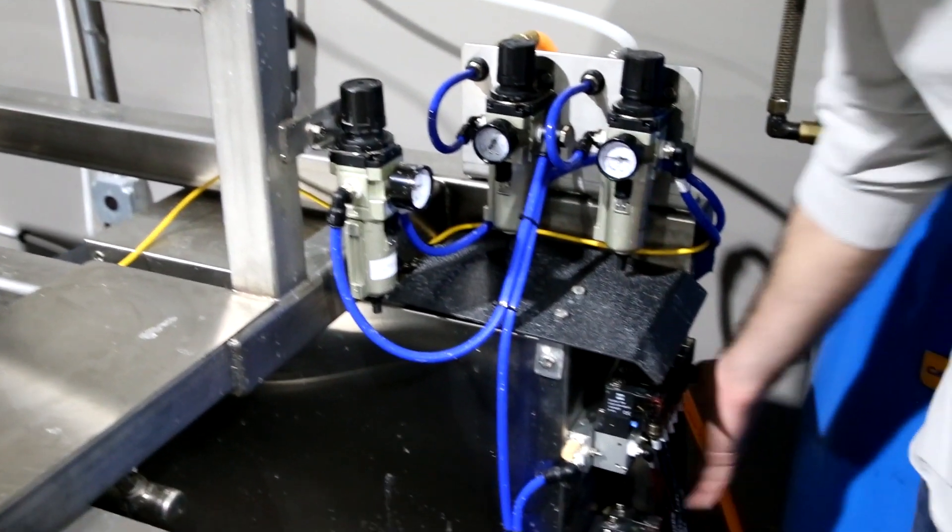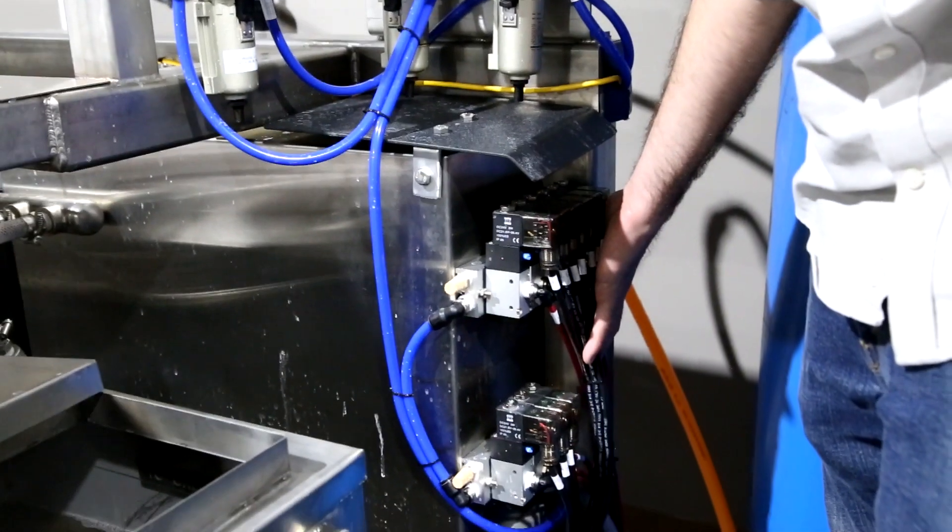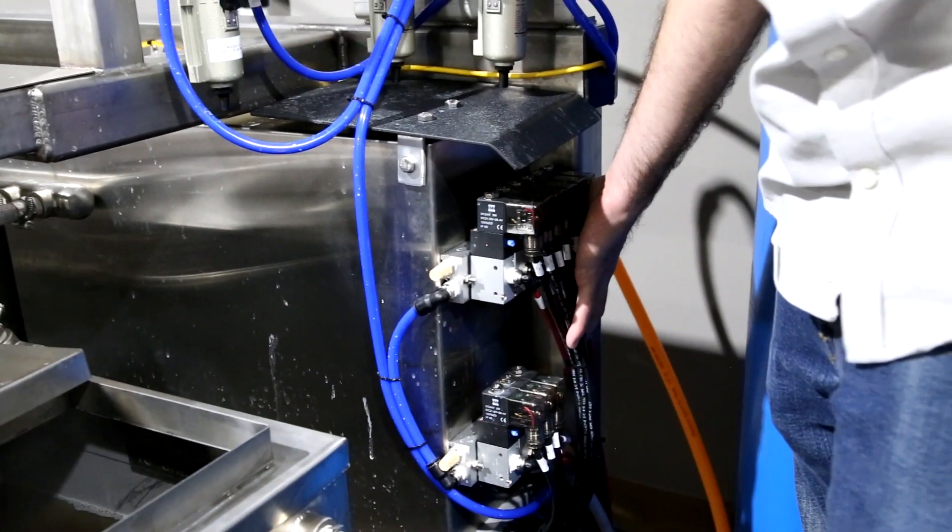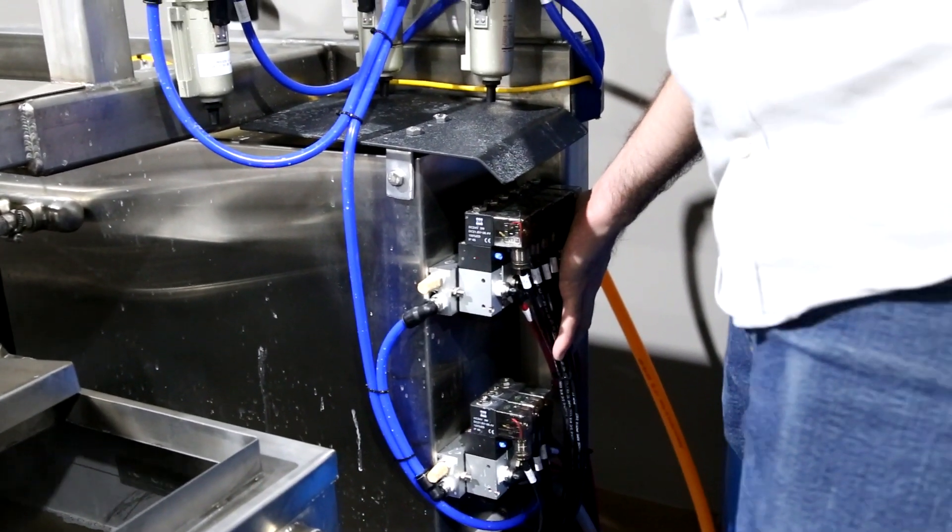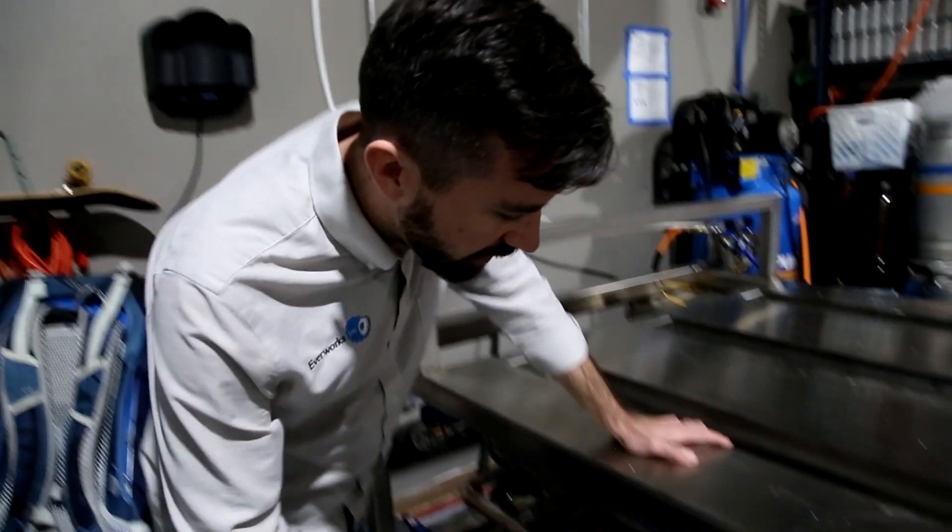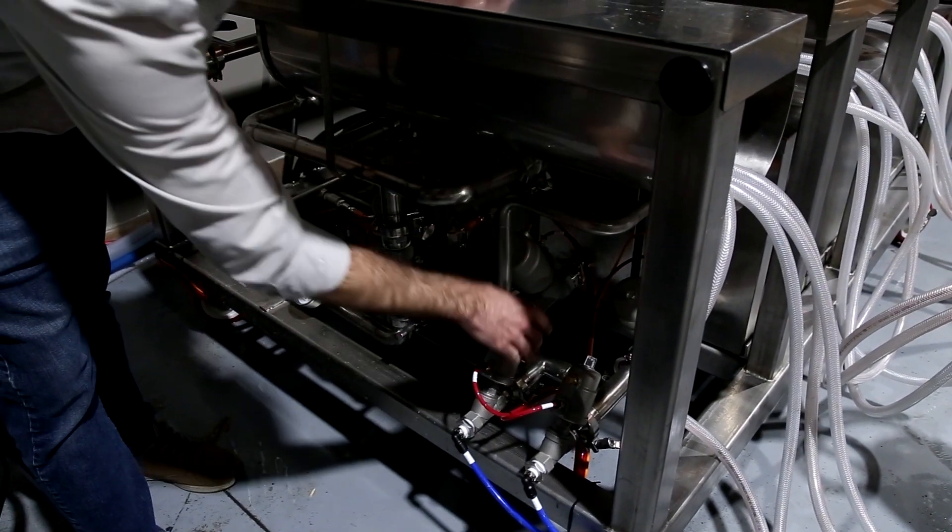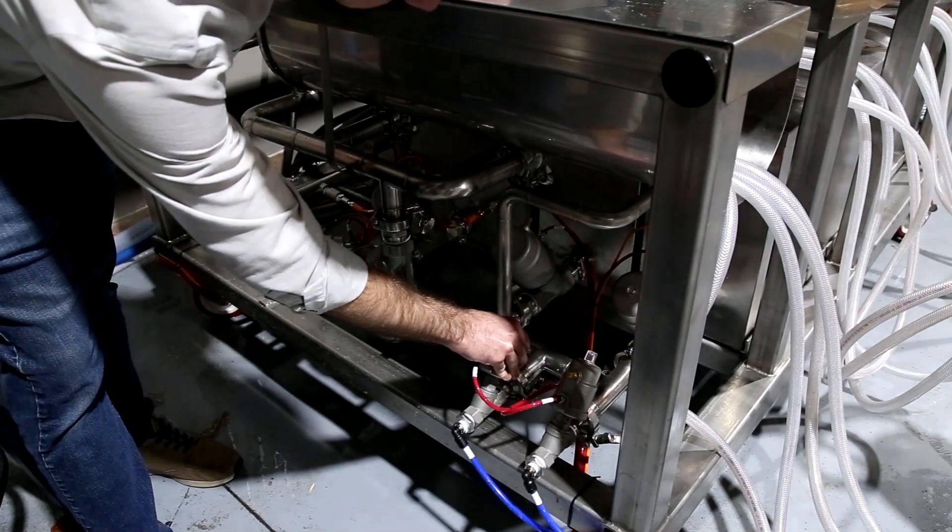Down below we have our solenoid bank manifold. All of these are 24 volt wash down rated and they control all of our angle seat pneumatic valves. On this side we have all of our custom fabricated stainless steel 304 tubing and all of our pneumatic angle seat valves.